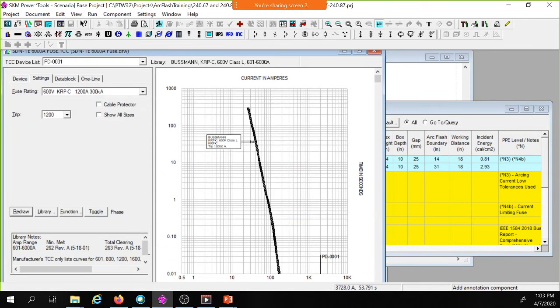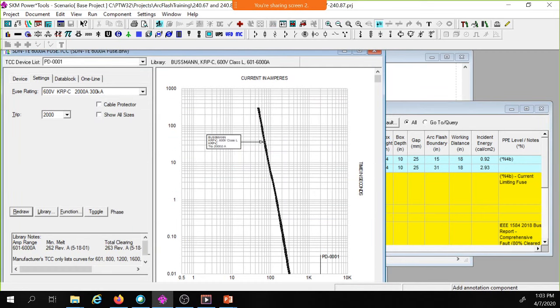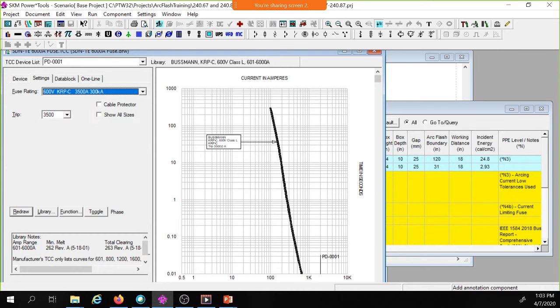I'm going to increase this to a 2000 amp fuse. My incident energy went up to 0.92. My clearing time is now 0.0083, at 40.87 kiloamps. I'm going to move this up to a 3,500 amp fuse. Now my incident energy is 24 calories. My clearing time is 0.257.